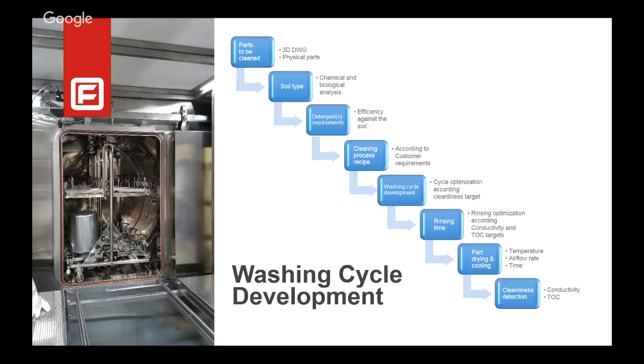One of the advantages of a pressure vessel is that for drying and cooling, we can apply the vacuum. So we make the evaporation of the residual water because of the vacuum in the chamber. And of course, we also heat the chamber with the jacket. During the process, the cleanliness level is detected by several parameters like temperature, air flow rate, time, and also, very important, the conductivity of the water that is leaving the chamber. And on request, we can also add a total organic carbon, TOC, that provides the efficiency of the washing.